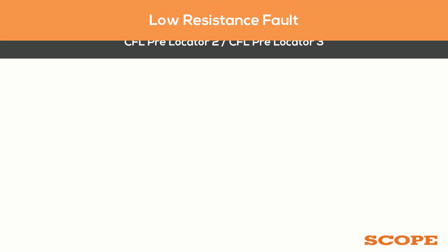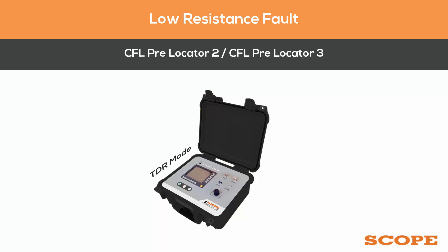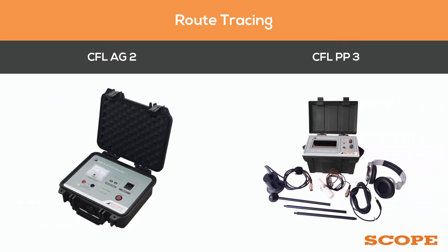If it's a low resistance fault, it is pre-located with CFL PL2 or CFL PL3 on TDR mode. After pre-location is done, route tracing can be performed using CFL AG2 and CFL PP3.